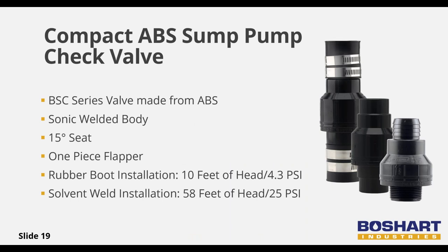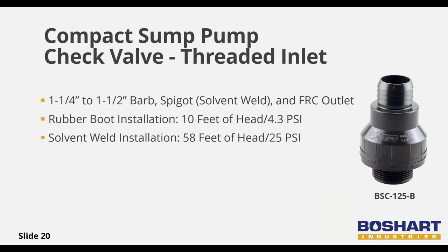All compact ABS sump check valves use a gravity-style design. They are constructed from two body pieces that are ultrasonically welded together, and the flappers are made of one piece to ensure a positive seal on the seat. These should all be installed in a vertical position so flapper operation is not compromised. Compact valves with threaded inlets may come with three outlet options: barbed for sump discharge kits, slip solvent weld, or an attached flexible coupler. If the flexible coupling is used, the line will need to be thrust blocked, and the pressure rating changes from 25 psi to 4.3 psi.